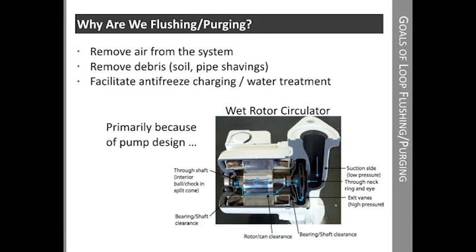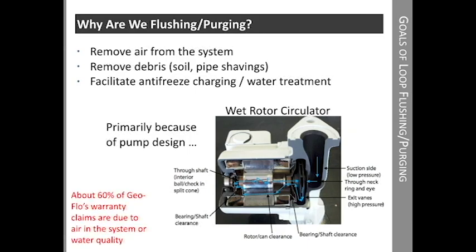Removal of air and debris is so important because of the pump design used for most geothermal systems. Wet rotor circulators are very common in the geothermal industry. This type of pump is cooled and lubricated by the fluid circulating through the system. As you can see from the picture, the passageways are very small and the clearances are tight, so any debris can cause premature wear and eventually failure. If the pump becomes air locked, it gets very hot and can eventually fail. About 60 percent of Geo-Flo's warranty claims are due to air in the system or water quality, which includes debris in the system.